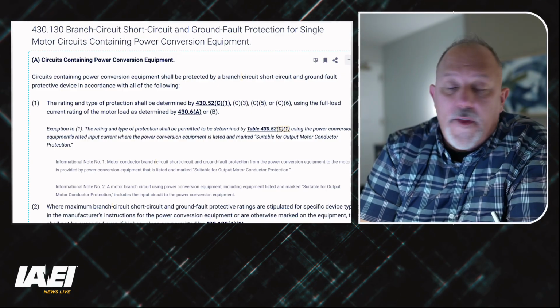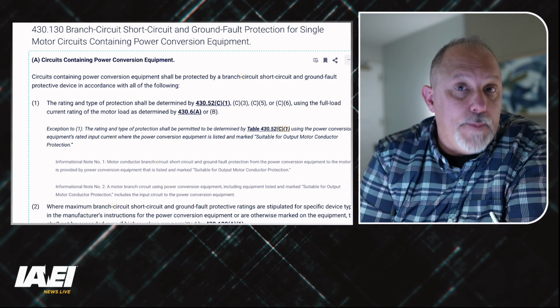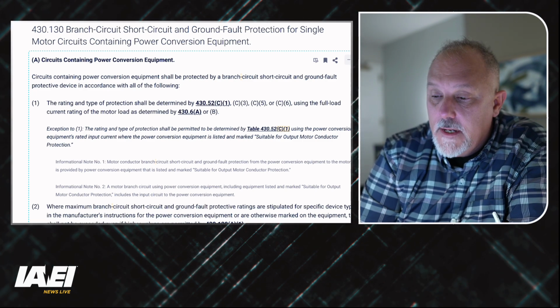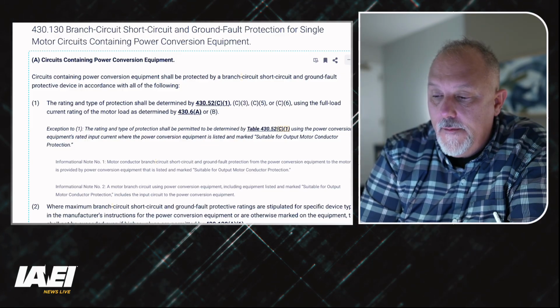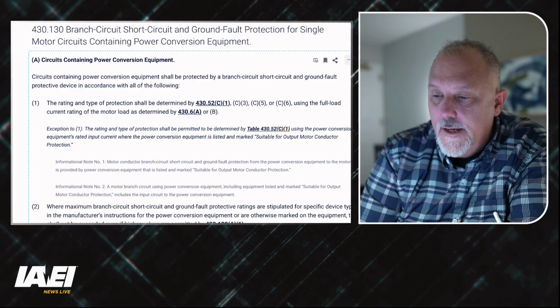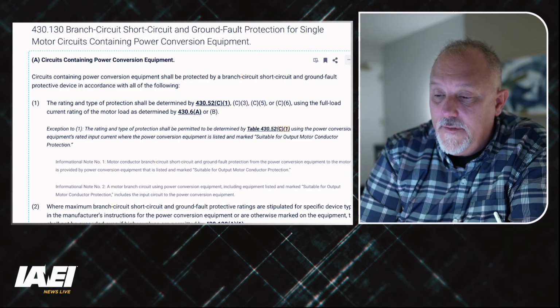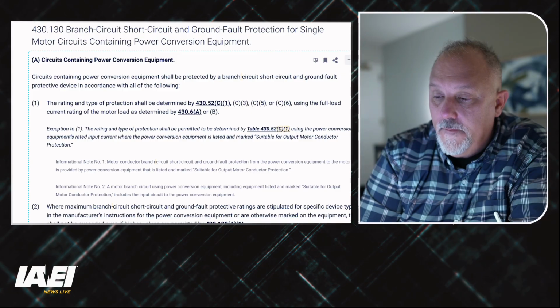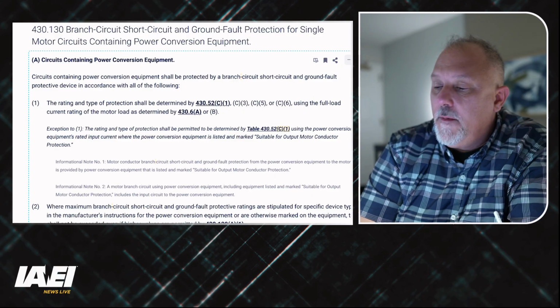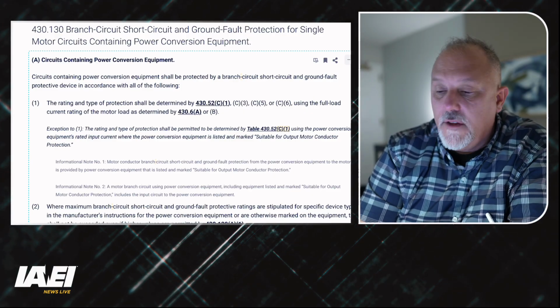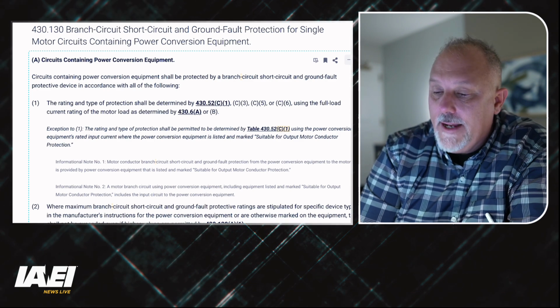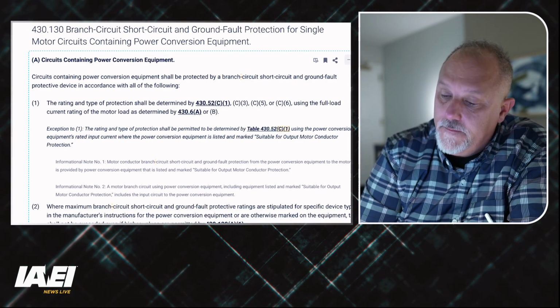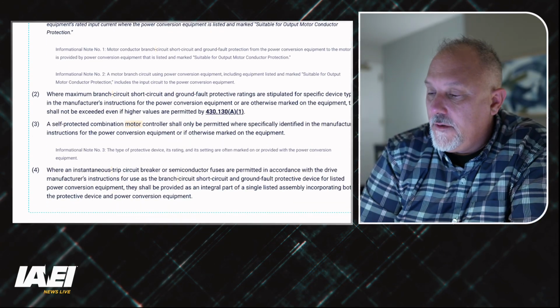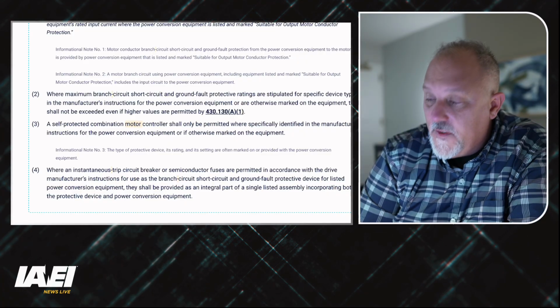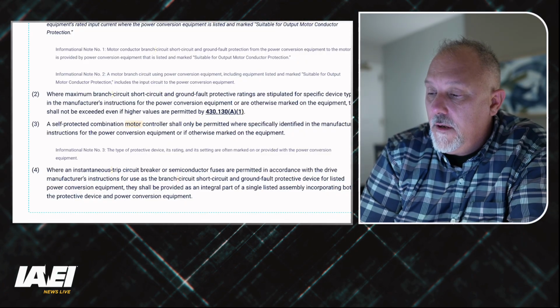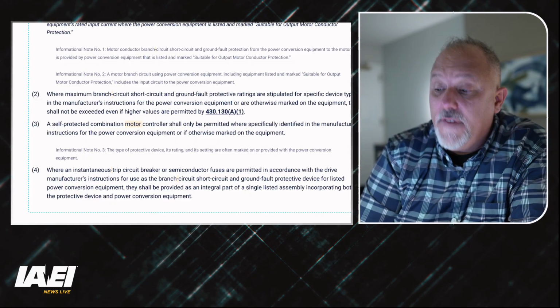So the first, 430.130(A), I would argue, is the branch circuit that's supplying the drive itself. And it tells you... no, it doesn't. This isn't the drive. Because it says the rating and type of protection shall be determined by 430.52(C)(1), (3), (5), or (6) using the full load current rating of the motor load as determined. So that's no drive in the picture. And then it says where maximum branch circuit, short circuit, and ground fault protection are stipulated for specific device types in the manufacturer's instructions, they shall not be exceeded even if higher values are permitted.